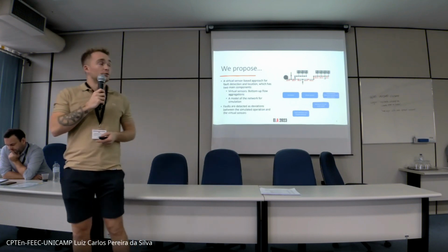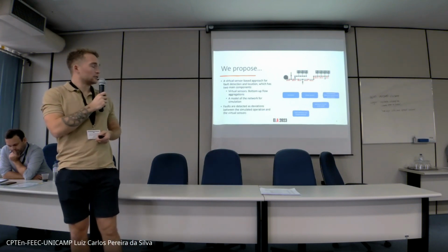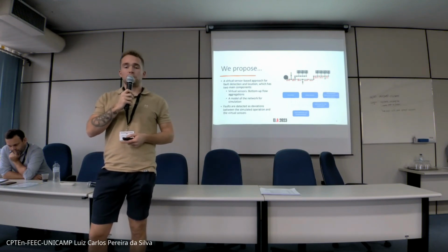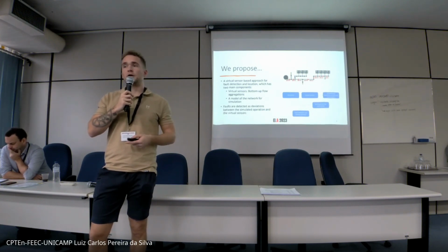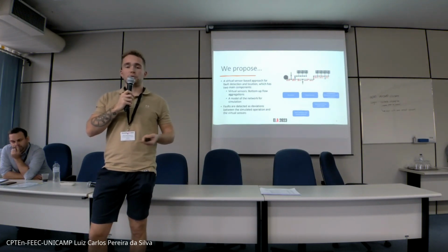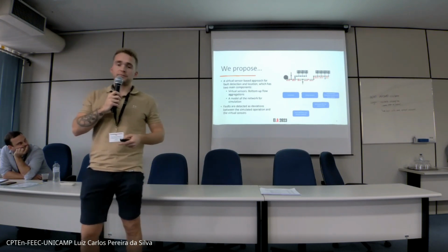If we look to the lower right corner, we see a schematic of the proposed approach. We'll use the virtual sensors to automatically determine clusters of consumers and their relation in a hierarchical sense. And then starting at the topmost cluster, we will start our fault detection and location protocol, in which we'll use the simulated flow measurements and the flow measurements from the virtual sensors for comparison.